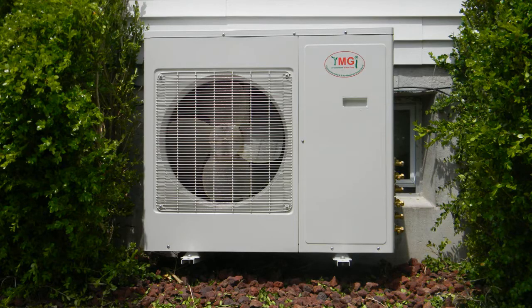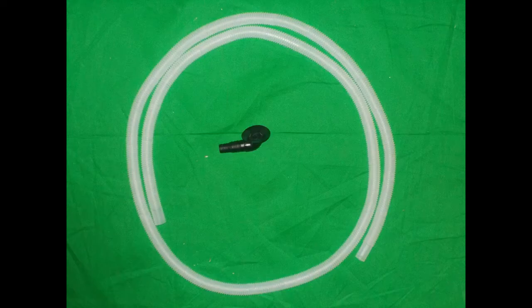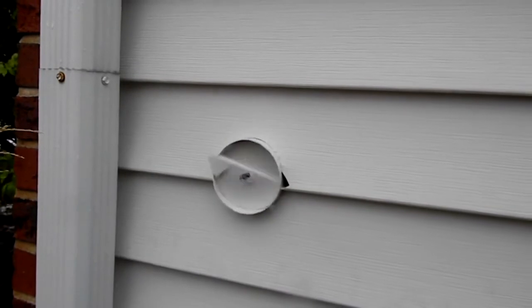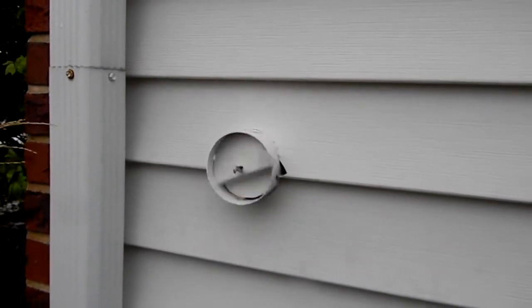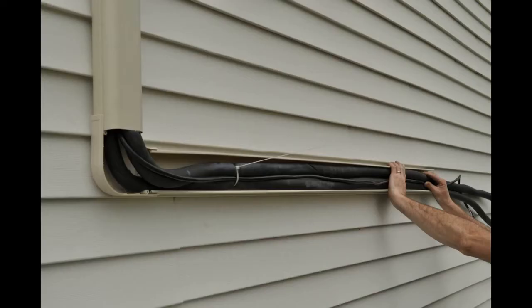For heat pumps, the unit must be raised from the ground to prevent the condensate from freezing on the coils and causing damage. We also recommend the use of a drain adapter and hose to divert the condensate away from the unit. After the hole has been drilled to the inside unit, we are ready to connect the tubing and the interconnecting wiring. For your refrigerant lines, use insulated ACR copper.